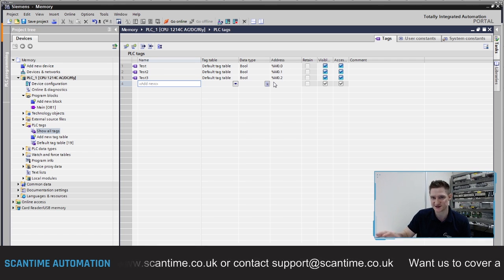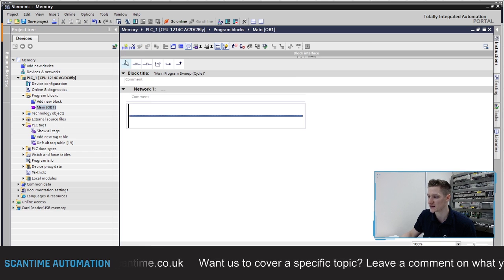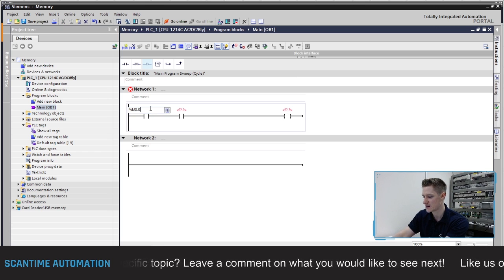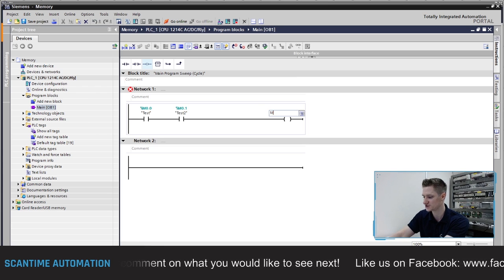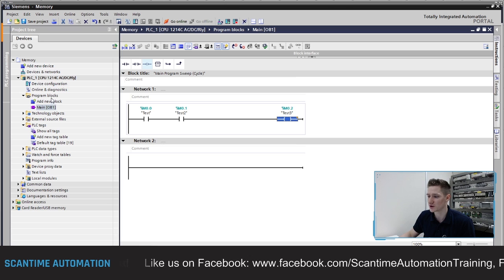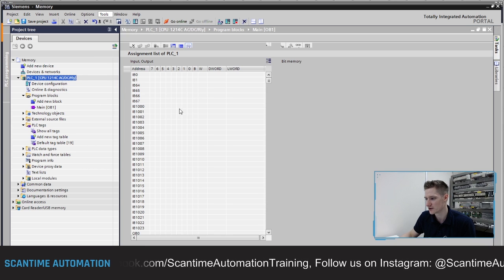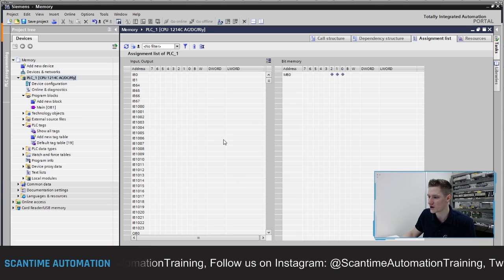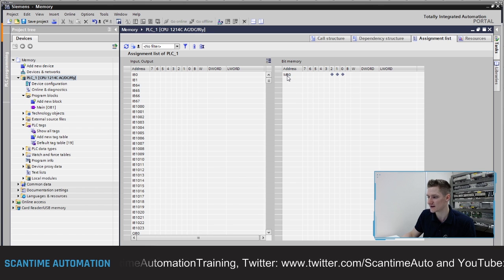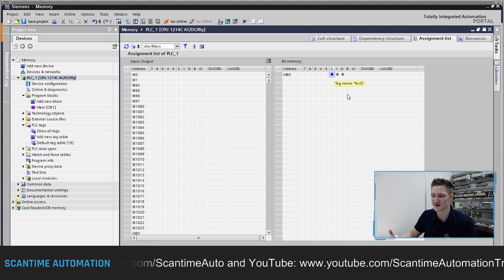Inside of Siemens we've got what we call an Assignment List, where we can actually see what bits we are assigning inside of the program. If I go into my program OB1 and create a basic program with two contacts going into a coil - using M0.0 and M0.1, when both are on they turn on M0.2 - we can then go to the Assignment List and see these bits being used. Go to Tools, then Assignment List. On the right-hand side we can see our internal bit memory addressing area, and we're using memory byte zero with these three bits.